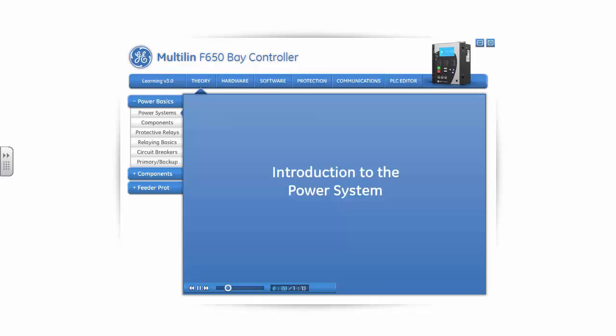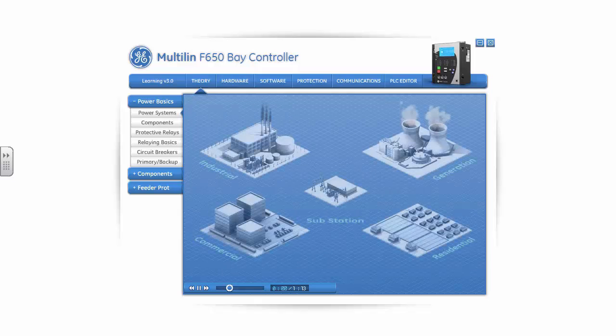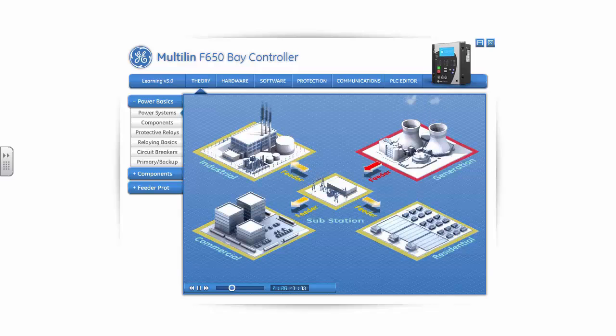Modern electrical power systems are remarkably dependable, delivering energy 24 hours a day, 365 days a year without any interruption. Protective relays have an important part in ensuring this continuous service. The protective relay is always ready to react instantly to protect the system from damage and to minimize any service interruption. To better understand how protective relays fit into the modern power system, we will first review the makeup of the system.